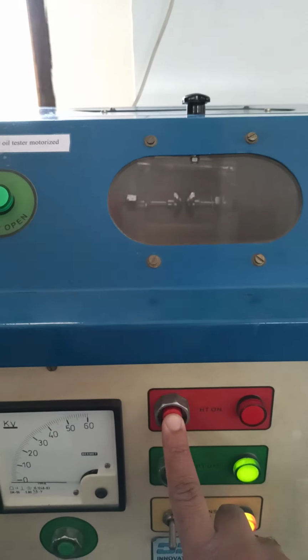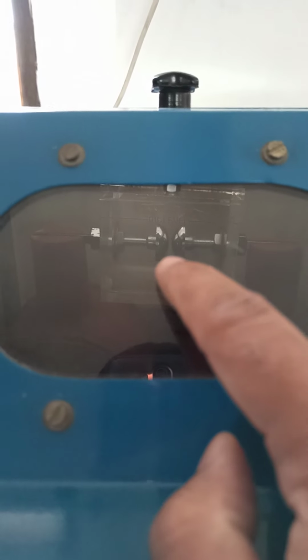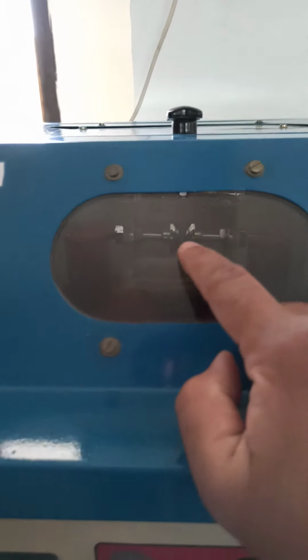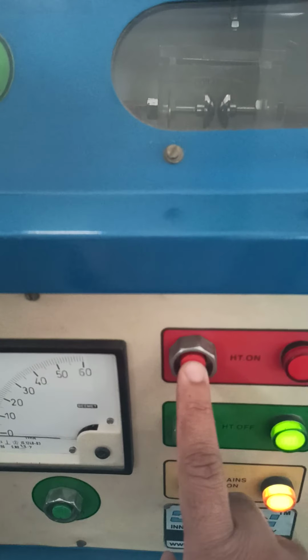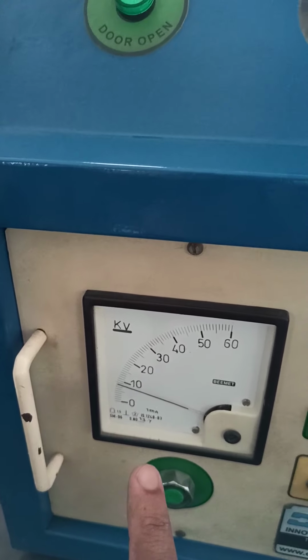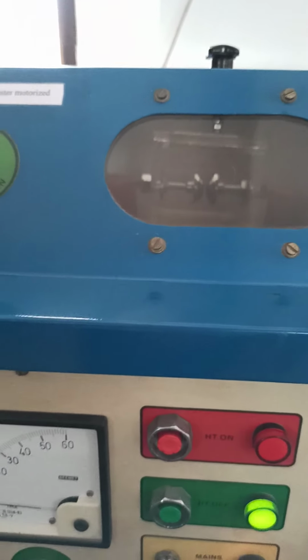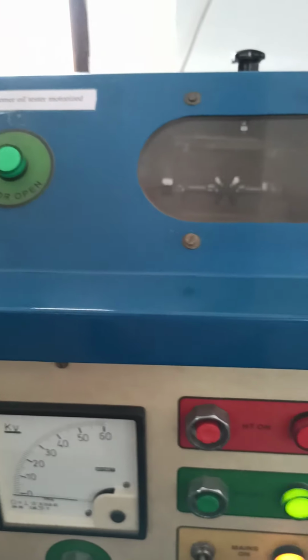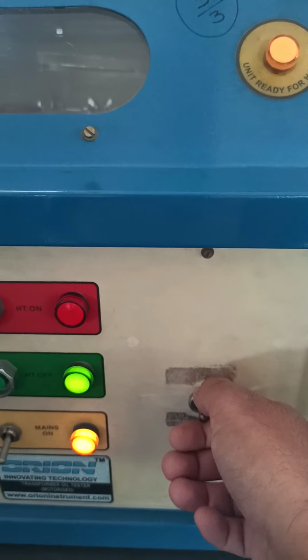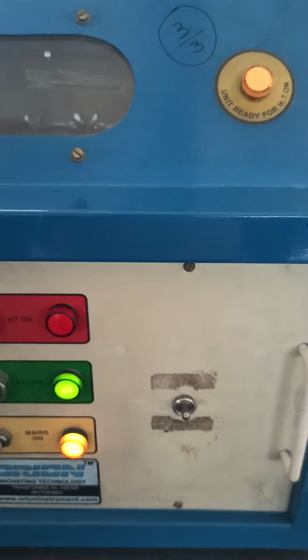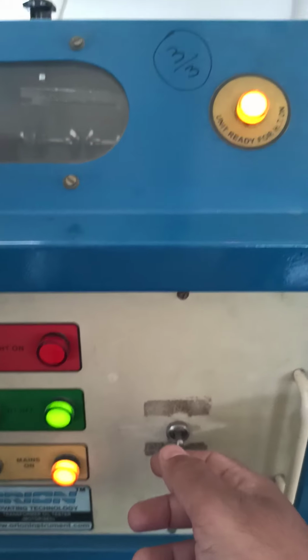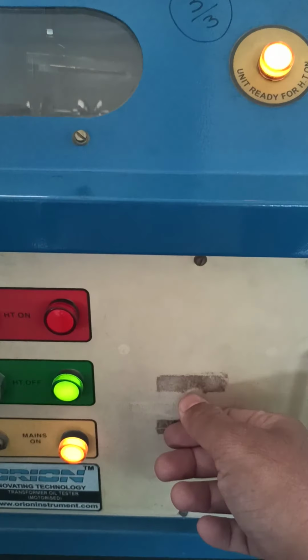I have to do the test. You can see inside that you will observe the arc also. Whenever the dielectric strength breaks, at that point you will observe the arc also. So I will show you that also. First I have to turn it on. So I have turned it on. You can see this meter is increasing, and again I will show you. Just a minute. Again I have to move the motor to the initial position, because the unit is not ready. Now it is ready for the test.